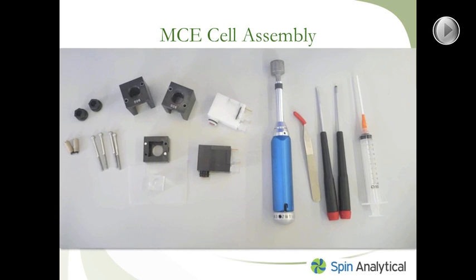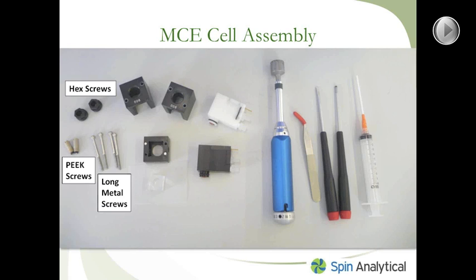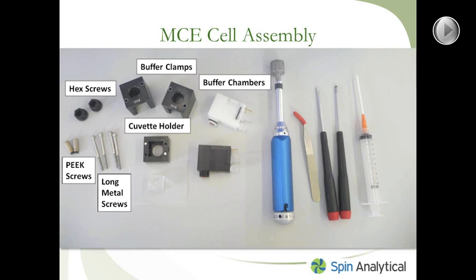In this image are the different components that make up the MCE cell assembly. On the right-hand side are also the tools required to assemble all the components. The cell assembly is made up of two hex screws, two PEEK screws, four long metal screws, buffer clamps made out of aluminum, and buffer chambers — there are two: the white one is the top buffer chamber, while the black one is the bottom buffer chamber. There's a cuvette holder that holds the quartz cuvette. The quartz cuvette has a sample chamber in the center with dimensions of two millimeters by two millimeters by four millimeters, and that's where you put your sample to be measured.